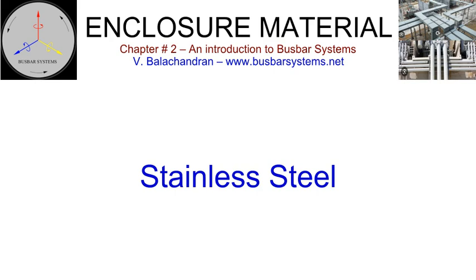Stainless steel enclosures, manufactured with grade Type SS316, have a higher corrosion resistance due to the presence of molybdenum and a higher content of nickel than grade Type SS304. The preferred material for stainless steel hardware is SS304 that has higher chromium content and is therefore much harder and wear resistant.